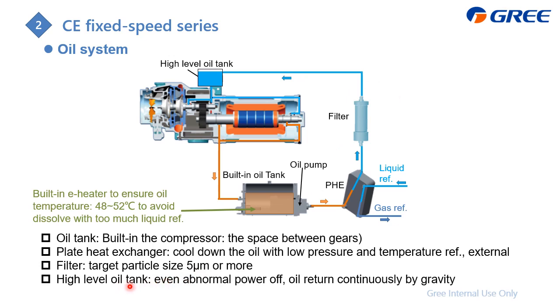And the last is the high level oil tank. Why do we need to put it here? If this centrifugal chiller has a sudden power failure, even at that time the oil can flow into the motor or the gears directly by gravity, which can ensure the lubrication.